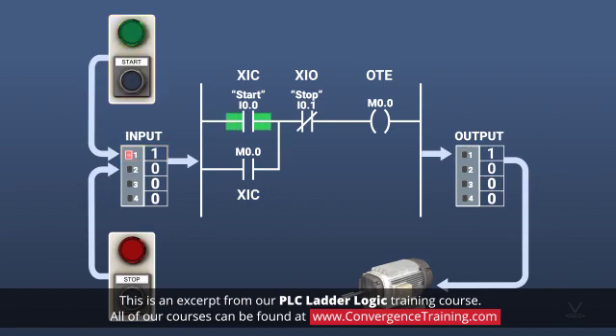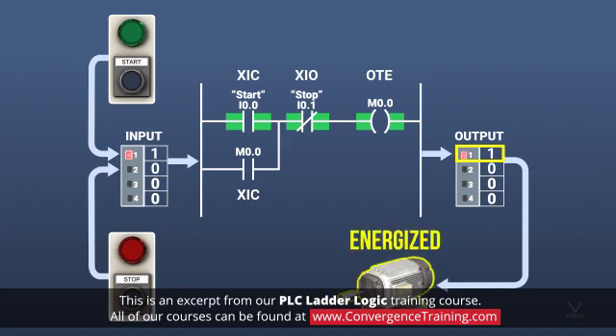The second instruction is an XIO. Since this data bit comes from a normally open stop switch, which has not been pressed, the input data value will be 0, and that instruction will also evaluate as true. Because both of the upstream conditions on the rung evaluate as true, the final instruction on the rung also becomes true, which translates into an output data value of 1 and a running motor.